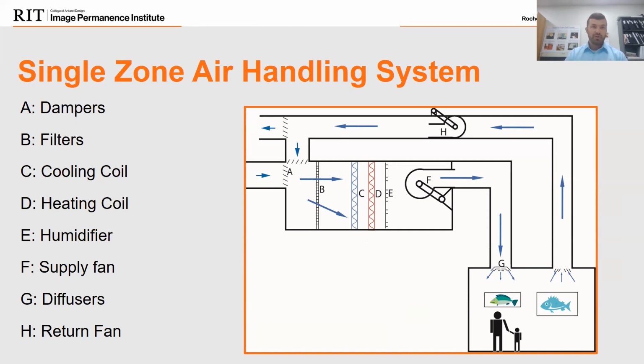We have seen larger systems with multiple thermostats being averaged, if you will. So if you imagine a large rectangular room and there's 4 or 5 thermostats that all are recording and taking an average temperature, and that temperature is what the unit's responding to. That large room may be conditioned and some of the thermostats may not be satisfied yet. One may be satisfied. So you may wind up with a dead zone, a microclimate, if you will, until all or most of the thermostats are calling for conditioning, and then the unit may either turn off or back on, depending.